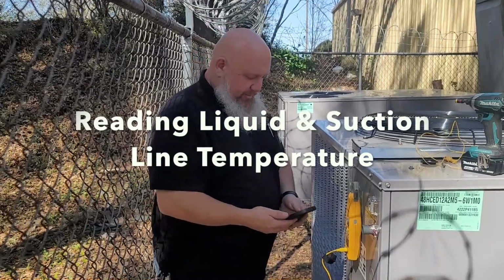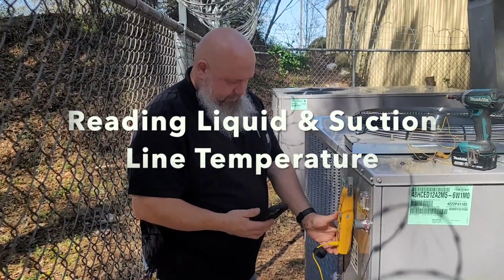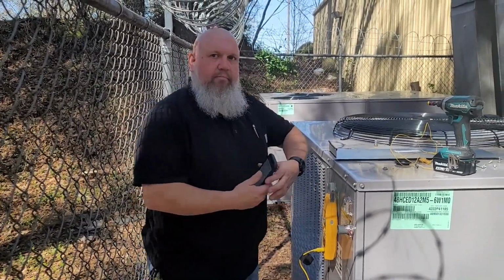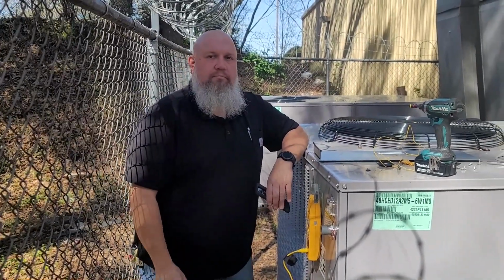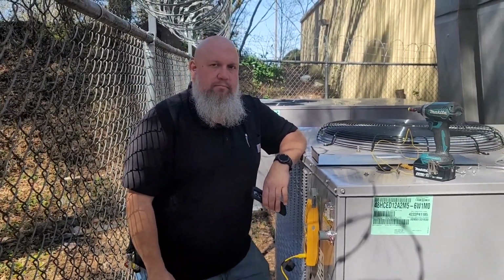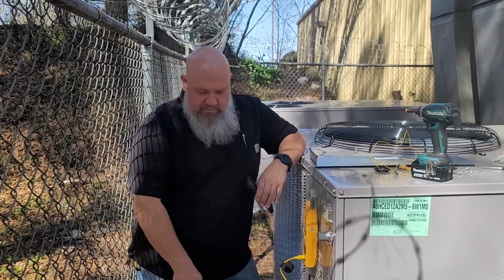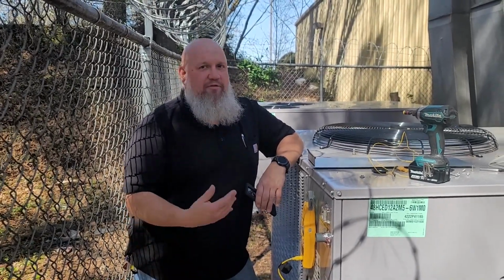What temp are you taking now? Liquid line temperature. Okay. And since you clamped on your clamps before the unit started up, how long does it take your meter to register the temp? As soon as you plug it in. It's been an instant reading. Right. Running about 10 minutes.